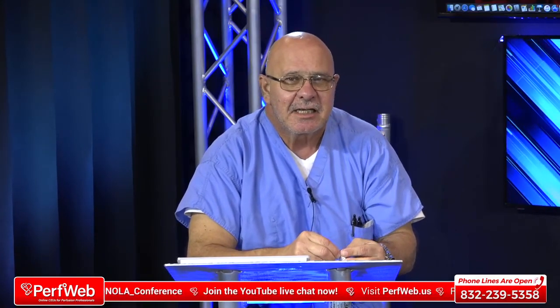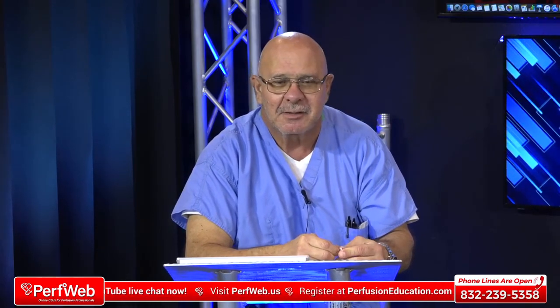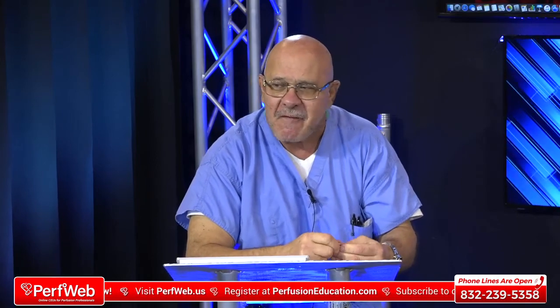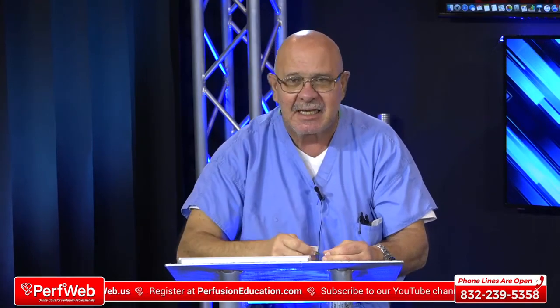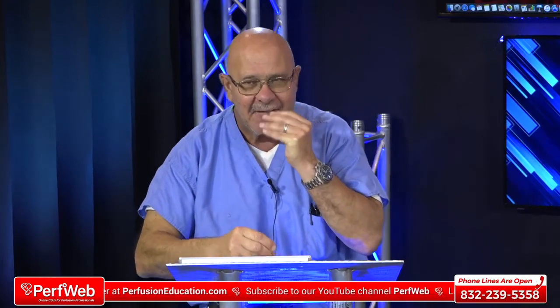So I hear this, and then a pop. And I looked over to my right, because that's where I was coming from, and I see the end cap, which had the oxygen line going from the halothane vaporizer to the oxygenator, had popped off. So I stuck it back on. Seemed a reasonable thing to do. And after about 5 or 6 seconds, maybe a little longer, I hear a pop, and it pops off again. So now I'm starting to get worried.